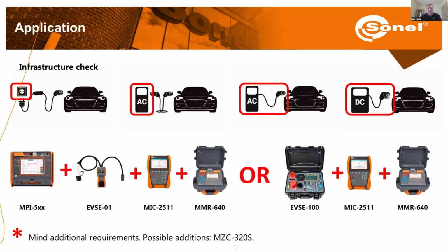Now, on the other hand, when we are mostly checking charging stations, then we can use the EVSE-100 meter. And in case of DC charging stations, additionally, we're going to need the MIC 2511 to check SPDs and the microohmmeter to check continuity using higher currents. Now, further on, when we are checking the charging stations more often, but sometimes we want to check the regular electrical installation, then the EVSE-100 meter has as standard a special adapter which changes the output plug from Type 2 into just banana connectors. And later we can connect regular test leads and check any electrical installation, like for example, a single phase or a three-phase socket, using just the test leads and pin probes.